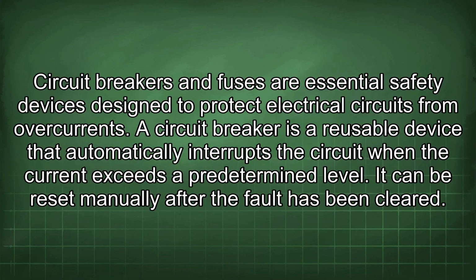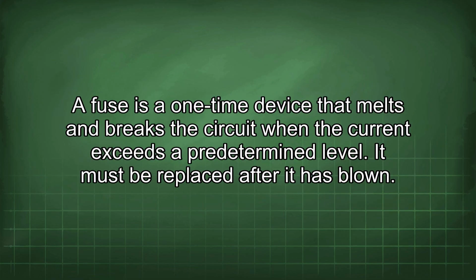Circuit breakers and fuses are essential safety devices designed to protect electrical circuits from overcurrents. A circuit breaker is a reusable device that automatically interrupts the circuit when the current exceeds a predetermined level. It can be reset manually after the fault has been cleared. A fuse is a one-time device that melts and breaks the circuit when the current exceeds a predetermined level. It must be replaced after it has blown.